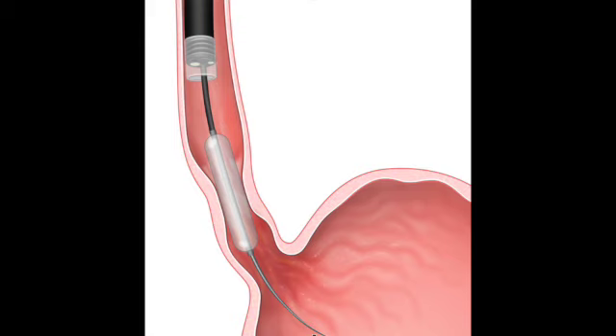Exactly. And if the tissue suddenly yields, that compressed air expands violently. Oh, man. So it creates this snapping effect. A huge snapping effect. And you lose all control over the diameter of the balloon at that exact second. Which is the last thing you want inside a fragile organ. Right. Water, however, is an incompressible fluid. This is the core principle of hydrostatics. So it doesn't compress at all. No. When the assistant pushes 1 cubic centimeter of water out of that syringe, it translates to an exact, immediate, and proportional expansion of the balloon. There's no spring effect whatsoever. None. The transfer force is 1-to-1, giving the team absolute microscopic control over the dilation.